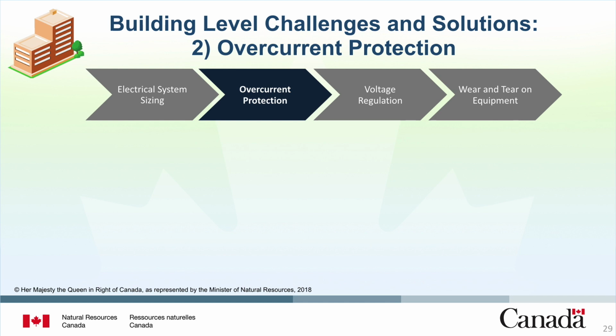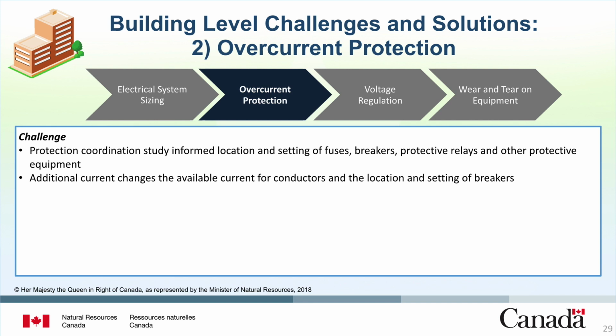Next, let's cover the challenge and solution related to overcurrent protection at the building level. Coordination of overcurrent protection is an important consideration in the addition of renewable energy generation. During initial distribution system planning, a protection coordination study informed the location and settings of fuses, breakers, protective relays, and other protective equipment synchronized to isolate electrical faults in a planned sequence. The additional current from a renewable energy generator invalidates previous protection studies because it changes the amount of current available for conductors to carry and changes the location and settings of breakers to prevent excessive current flow.